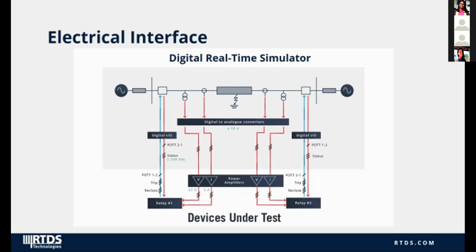Here, the digital real-time simulator sends voltages and currents, as well as circuit breaker status, from the simulation to a protection relay outside of the simulation. The breaker trip and reclose signals go from the physical relay back into the simulation to close the loop.